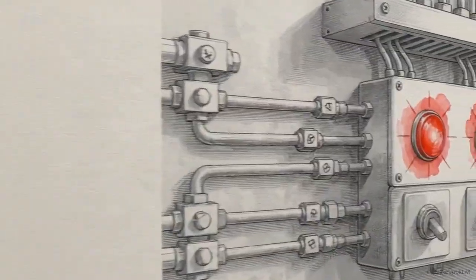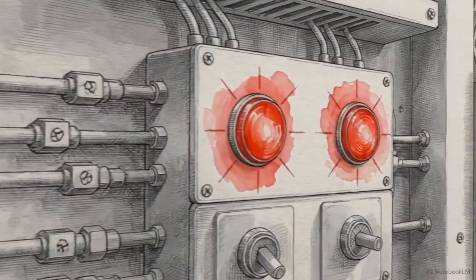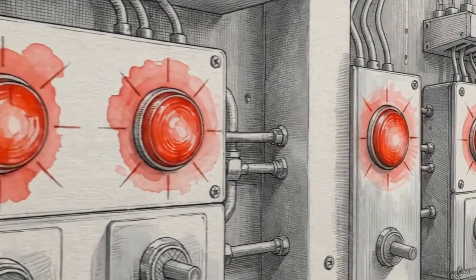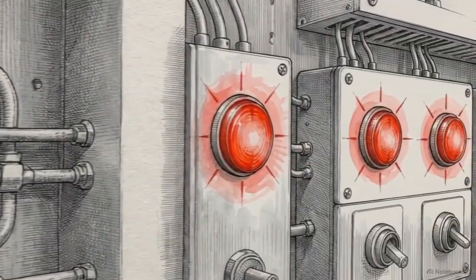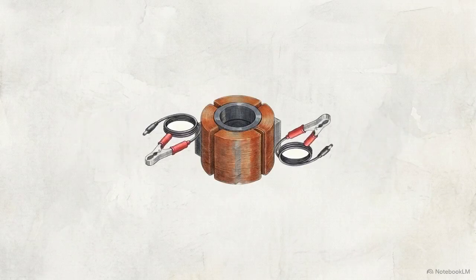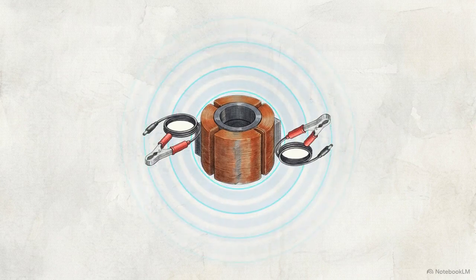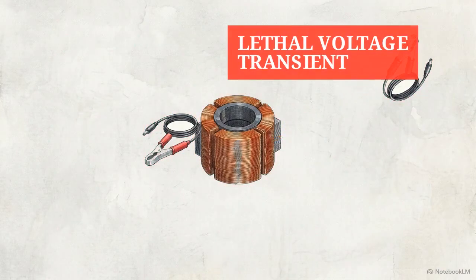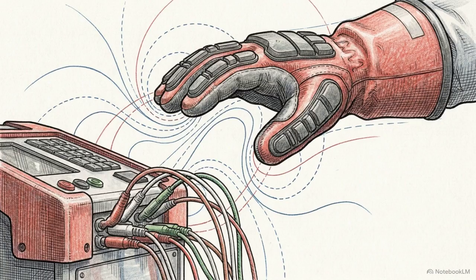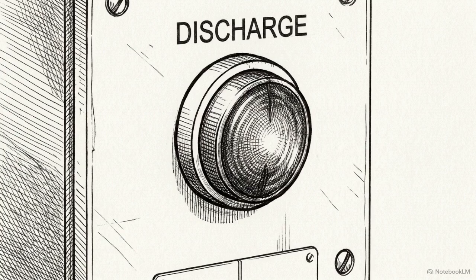Flawless execution is the goal, but commissioning engineers must also be prepared to manage extreme hazards when the physics behave unexpectedly. During DC injection, the highly inductive core stores massive amounts of energy. If a measuring circuit is disconnected while current is still flowing, the collapse of the magnetic field generates a lethal voltage transient, known as inductive kickback. To manage this, a strict shutdown protocol is enforced. Operators are forbidden from touching any test leads until the test equipment's discharge LED has completely extinguished, confirming the energy has safely dissipated.